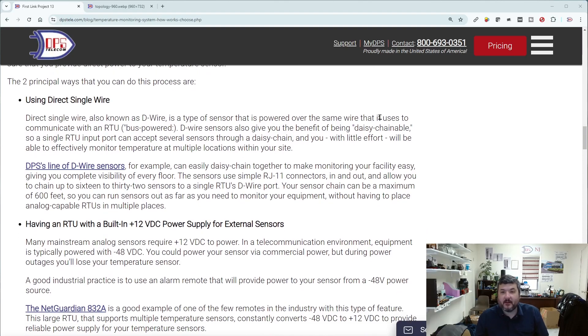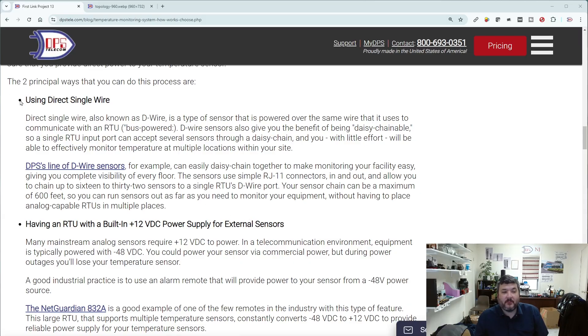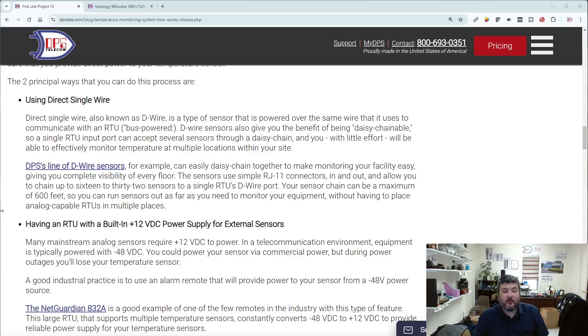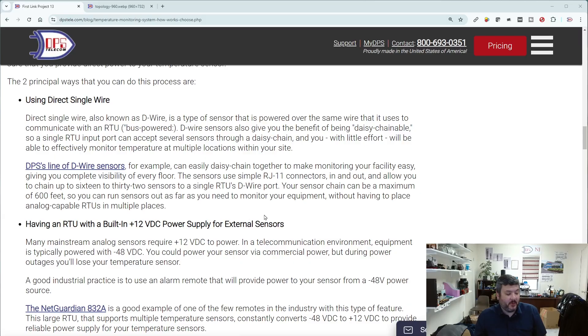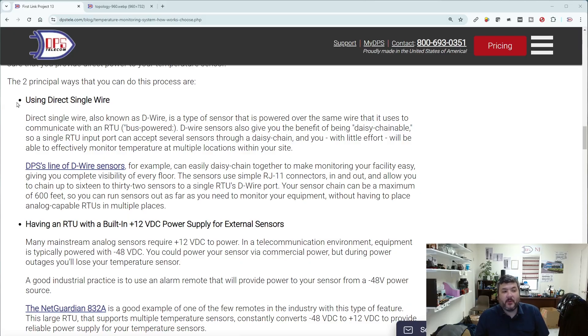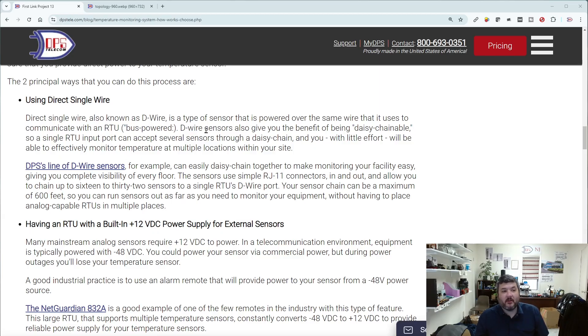With analog sensing, it probably needs power, but that's not incredibly difficult. This section describes two different things you can do. You can run a wire to the device itself. Some of our NetGuardians have a built-in 12 or 24 volt power supply to give power to a sensor. Even if you're a telecom and you have minus 48 volt sites, we will do a little bit of voltage conversion for you, because it is one of the frustrating facts about sensors - sometimes they want a different voltage than you natively have out at the site.